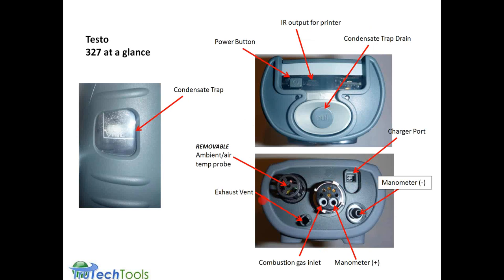So let's take a look at the side of the meter now. I talked about the water trap before. Here's that max line in the condensate trap, or the water trap, so you can see if the water gets above that level, you have a chance of sucking the water into the pump. If you suck it into the pump, it could gum things up, so you don't want to let it go there. You want to make sure that the condensate never goes above the max line.